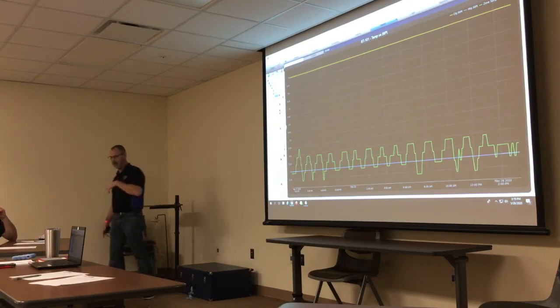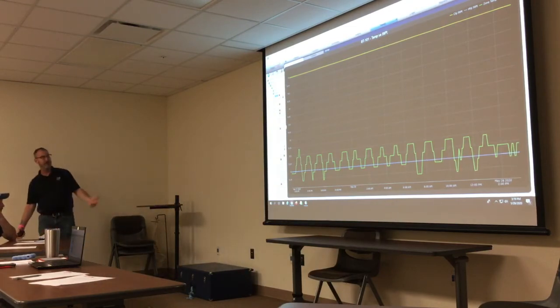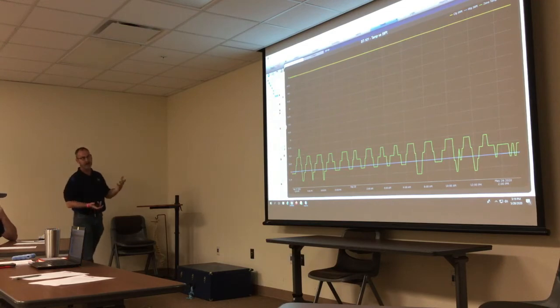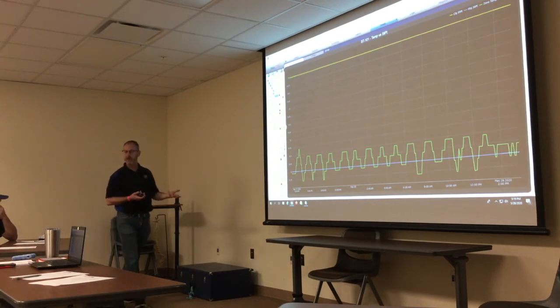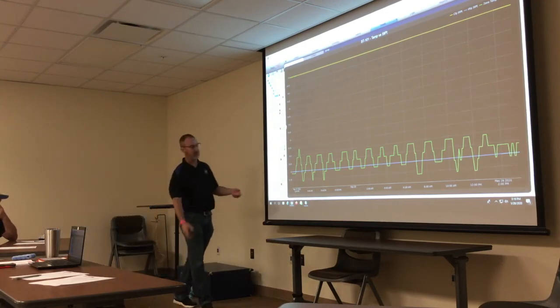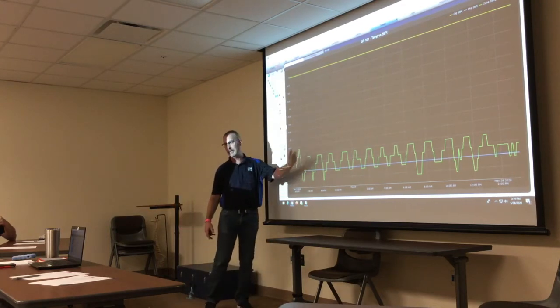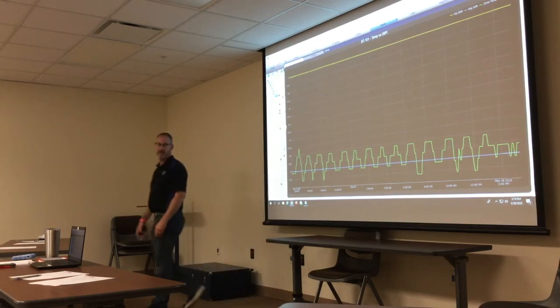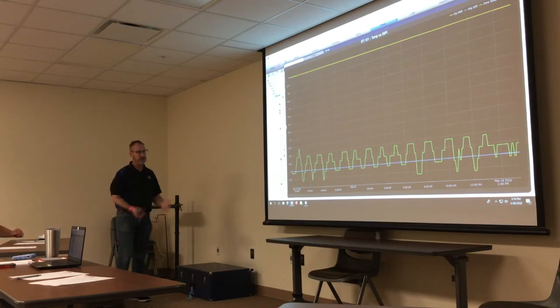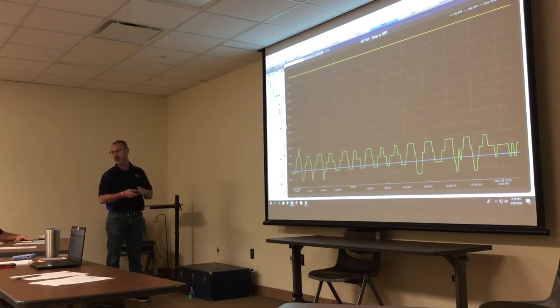Here's a trend that I created, and I created this one on every piece of equipment that has a thermistor. It's just the temperature in the space versus the set point, so you can see if I'm controlling to the set point, if the piece of equipment is controlling. This one has three points of data.